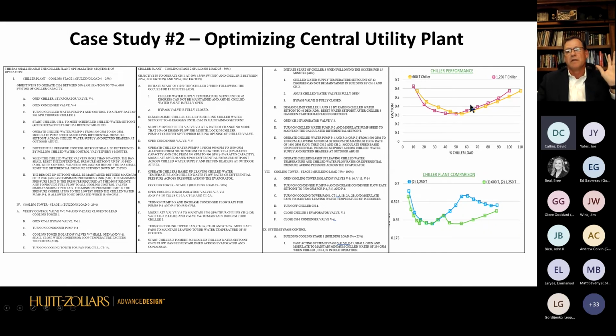If you look at these two lines here, on this y-axis, this is the power that consumes from 0 to 100%. You can see a 600 ton, 1200 ton, it's about the same. They're really efficient at 0.6 kW. These are really good machines, but they get really good if you're around 35 to 75%, down in this area.